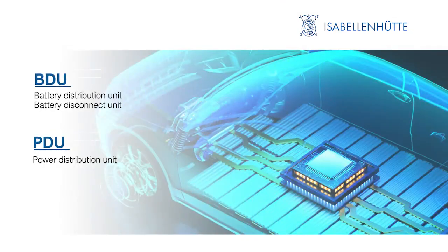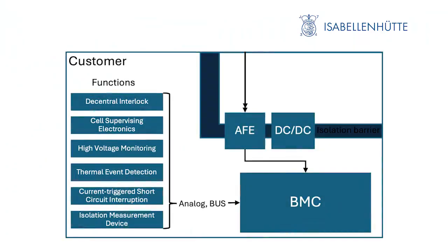The analog signals are transferred from the sensor to the analog front end of the main BMS via interface and pre-assembled cables. When measuring current using shunts, the high voltage side of the shunt and the low voltage side of the BMS must be isolated at the analog front end, indicated by the insulation barrier here.